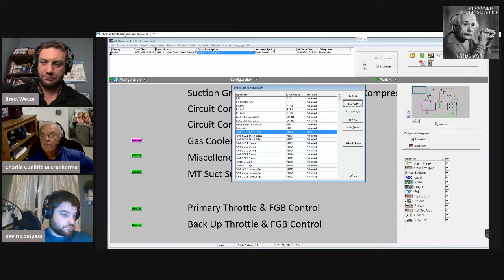So let's see, we did the node statistics. The analyzer, this is something I think, Brett, you were asking about. This is another analyzer. What this will do is give you the amount of updates, and you see right here in red, so I'm going to hit refresh. This will tell you if a node, maybe because of high voltage interference or whatnot, has been corrupted and is talking too much. If you see like 20 or 30 or 40,000 updates, that's a node that's gone off kilter. So if you're in the 1400s or the 1300s or down in single digits, that's a node that's working fine.